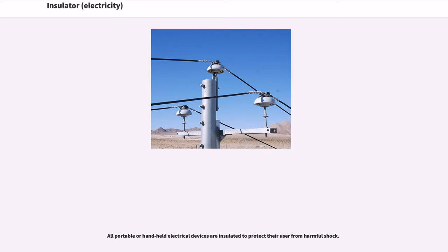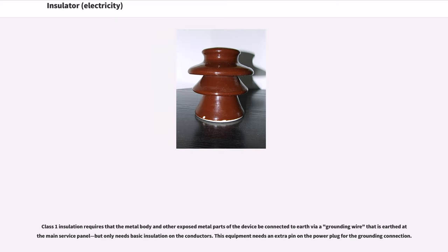All portable or handheld electrical devices are insulated to protect their user from harmful shock. Class 1 insulation requires that the metal body and other exposed metal parts of the device be connected to earth via a grounding wire that is earthed at the main service panel, but only needs basic insulation on the conductors. This equipment needs an extra pin on the power plug for the grounding connection.